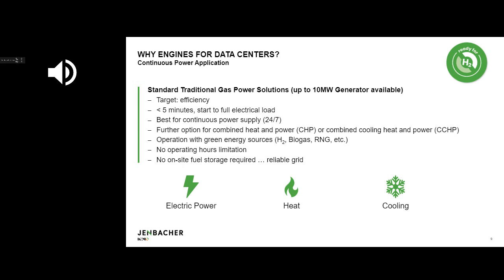So the traditional application we talked about before, backup, would now be a continuous application where the idea is to operate the unit 24/7. Here the fast start or transient capabilities are not that important because you will operate the unit on continuous or baseload applications. So the target here would be the efficiency of the unit.